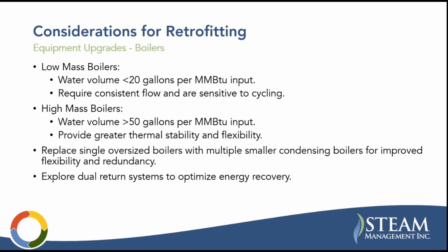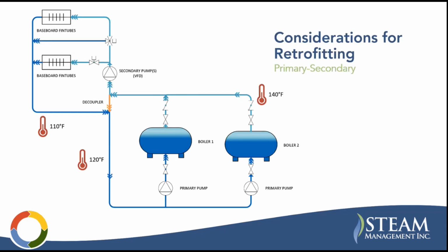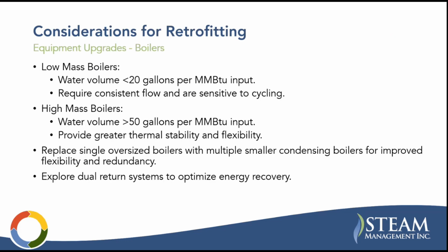Some other considerations: they have categories of boilers that are low mass, mid mass or high mass. Basically, low mass boilers have a water volume of less than 20 gallons per million BTU. So they have less thermal inertia. They require more consistent flow and are more sensitive to cycling. This is actually a benefit of the primary-secondary system: you can install these types of boilers and separate the flow of this loop from this loop, so you can get that flow requirement through your primary loop. High mass boilers have a water volume greater than 50 gallons per million BTU input. They have more thermal inertia, so they have better thermal stability and more flow flexibility. This is just something to consider when you're sizing. You can offset the change in volume with a thermal buffer, or a buffer tank, which we'll talk about in a minute.